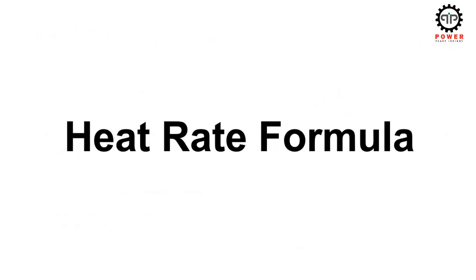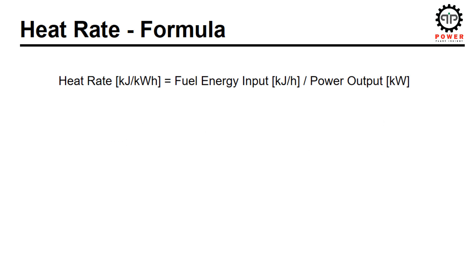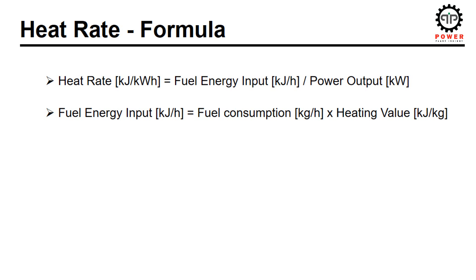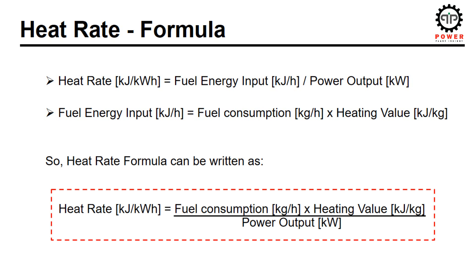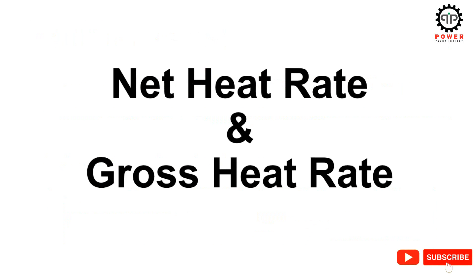Heat rate formula: from the discussion so far, we can write the heat rate formula as the ratio of fuel energy input to electrical energy output. The value of fuel energy input is obtained from the product of fuel consumption in tons per hour or kilograms per hour with its heating value in kJ/kg or BTU per pound. Use of lower heating value or higher heating value in heat rate calculation depends upon what is agreed in the power purchase agreement. So the final heat rate formula is the ratio of fuel consumption multiplied by its heating value, divided by the power output.